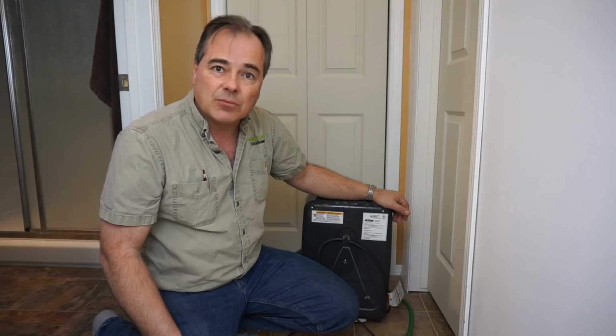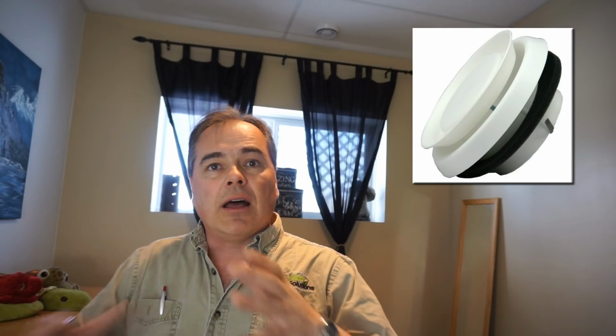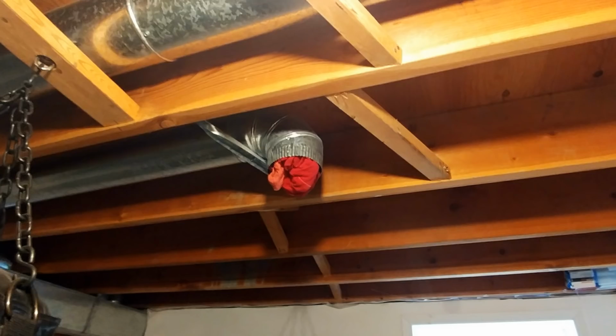Furnace ventilation in your basement. Quite often, basements are finished by the homeowner and may not have the skills required to properly install ventilation throughout the basement. Now you can see here above me there is a vent in the ceiling. That vent actually has a diffuser on it, which will blow the air across and throughout the room more evenly. Now quite often I'll go in for inspections and I'll see these kind of vents without the diffuser and with a rag or a bag covering that.